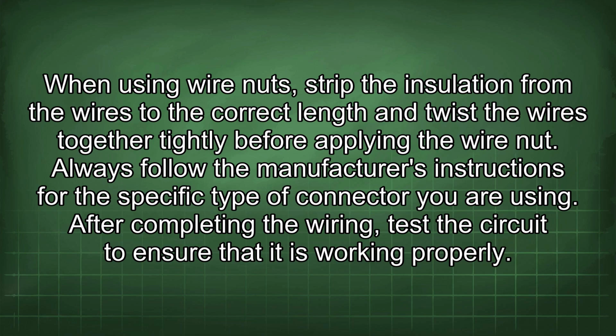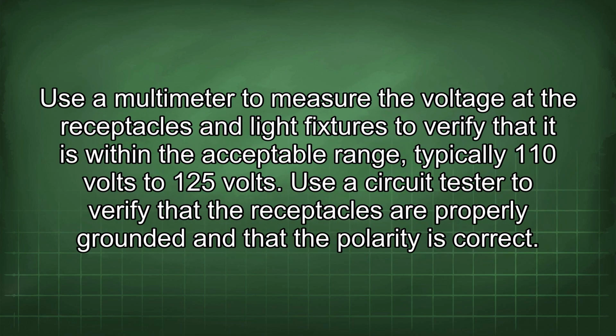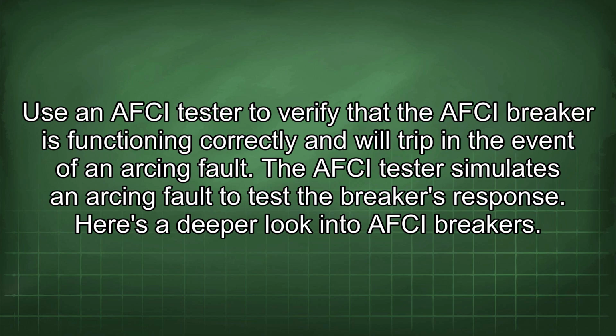After completing the wiring, test the circuit to ensure that it is working properly. Use a multimeter to measure the voltage at the receptacles and light fixtures to verify that it is within the acceptable range, typically 110 volts to 125 volts. Use a circuit tester to verify that the receptacles are properly grounded and that the polarity is correct. Use an AFCI tester to verify that the AFCI breaker is functioning correctly and will trip in the event of an arcing fault. The AFCI tester simulates an arcing fault to test the breaker's response.